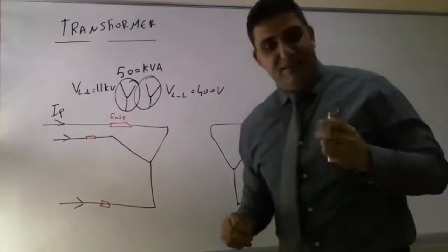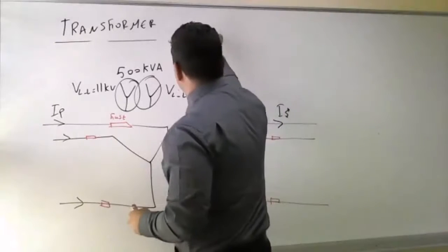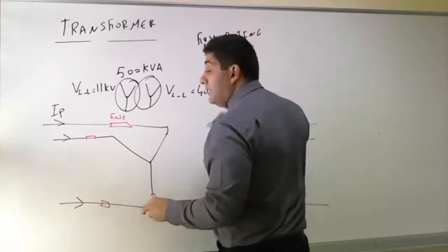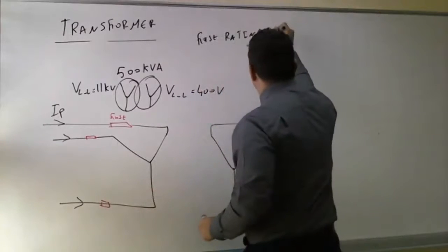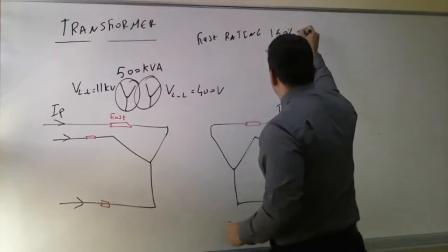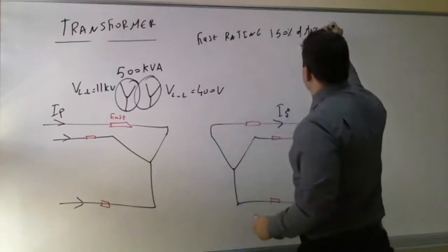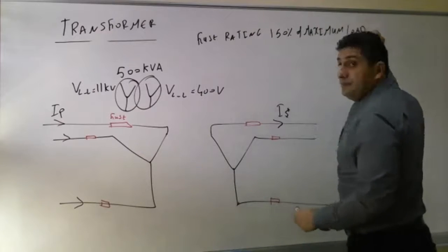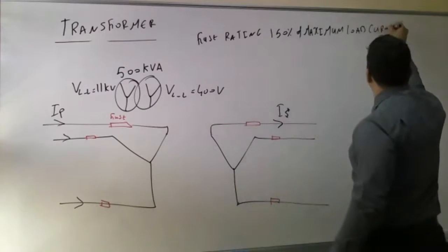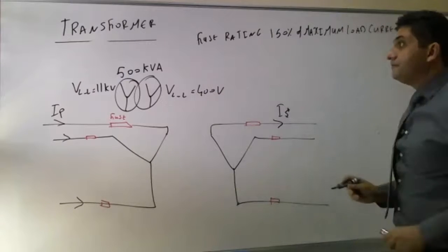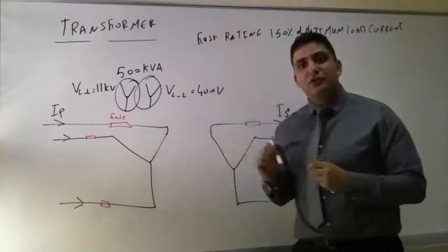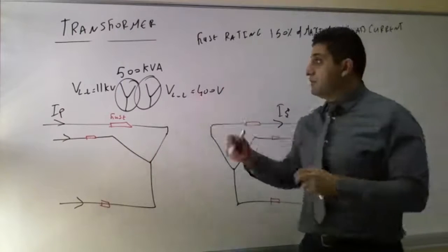Typically, the fuse rating is based on 150% of the maximum load current. That's my fuse. So I apply 3-phase analysis to determine the fuse rating.